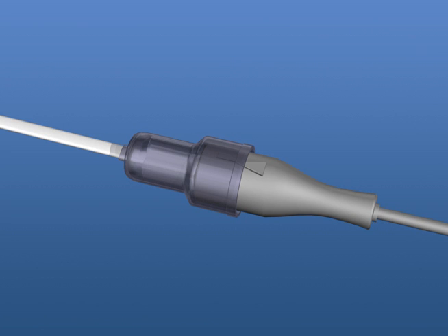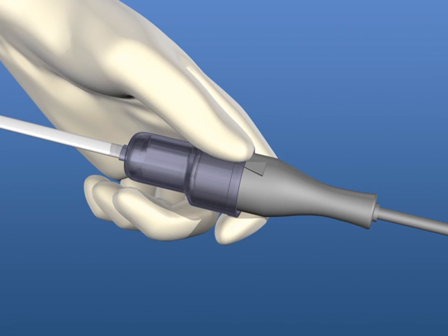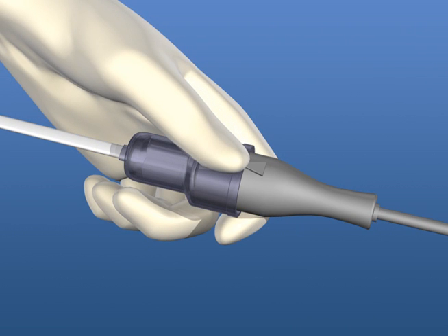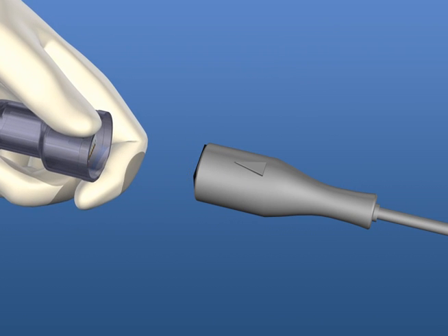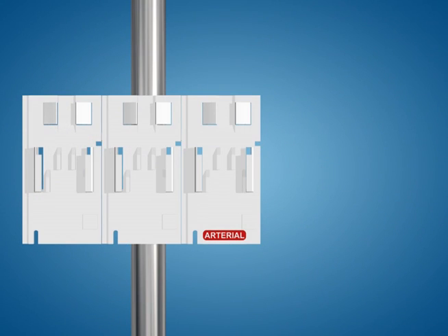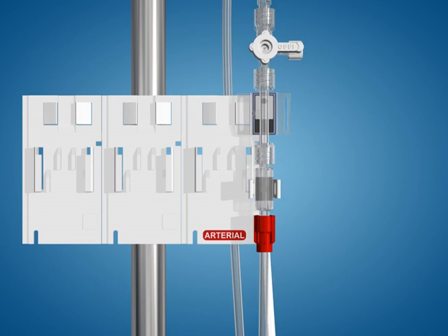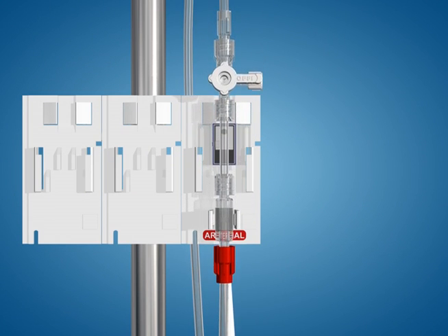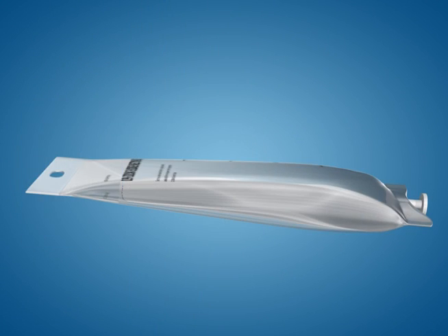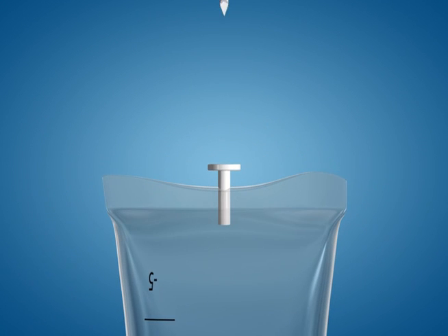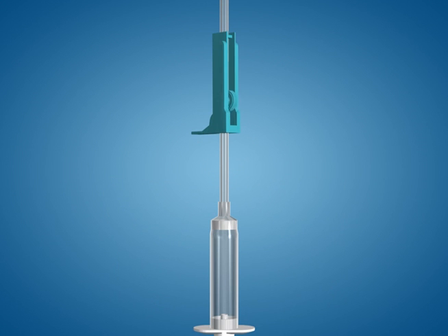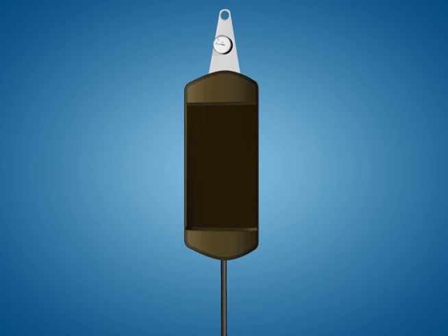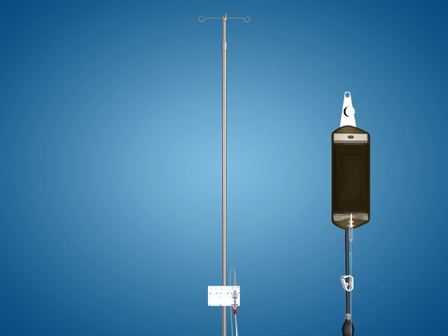To disconnect the cable, simply press the phone jack type locking mechanism in the Transpac 4 cable boot to release and pull apart. Place the transducer into the pole mount by sliding the wings of the Transpac 4 into the slots. It locks in place with a snap. Invert the IV solution bag and spike the administration set into it. Close the roller clamp that is up by the drip chamber and place the bag in the pressure cuff, but don't inflate it yet. Raise the IV bag about 2 feet above the transducer.